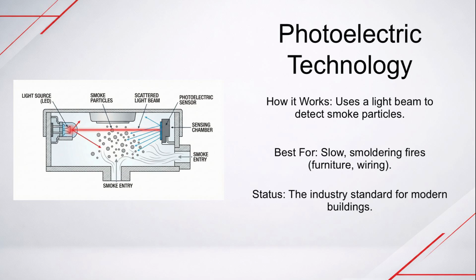Now, how does it actually smell smoke? There are two main technologies you need to know. The first, and most common type in modern buildings, is photoelectric. These detectors work by shooting a tiny beam of light across a sensing chamber. Under normal conditions, the light goes straight across. But when smoke enters the chamber, it hits that light beam and scatters it in all directions, reflecting it onto a sensor. Photoelectric detectors are excellent at detecting slow, smoldering fires, like burning furniture, melting wiring, or heavy smoke, which are the most common types of fires in commercial buildings.